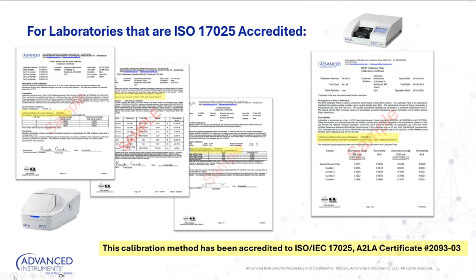Okay, so I asked the question at the start of this, what is the difference between calibration and verification? Hopefully we guided you through this in a nuanced way. Calibration is a traceable measurement consisting of a defined number of replicates with specified tolerance limits, and may or may not consist of physical adjustments. And that's the key. I think most people think calibration involves physically changing something. That is so far from the actual fact. Calibration just means that we are within the tolerance limits that we set, and that we're showing those tolerance limits in a uniform way.